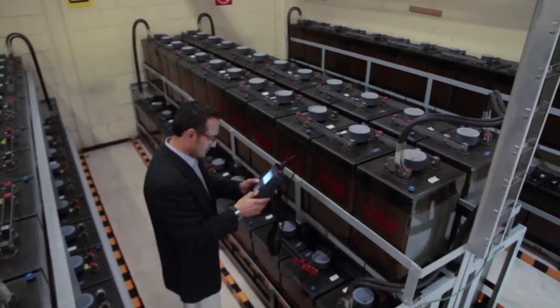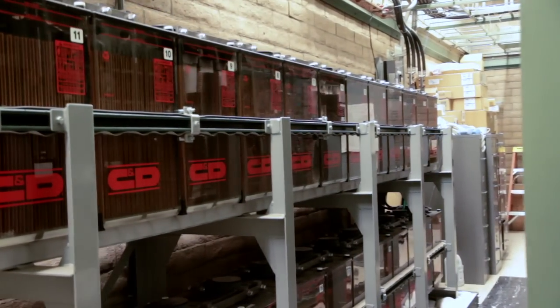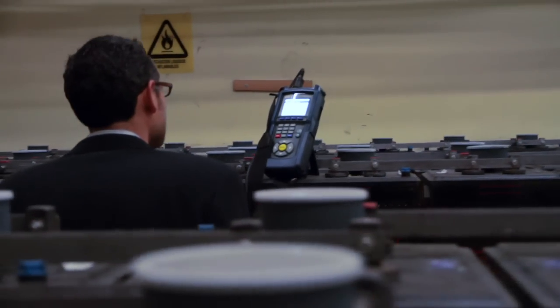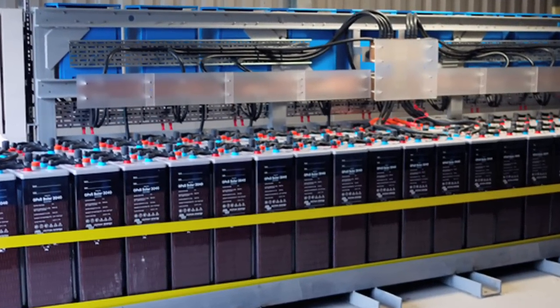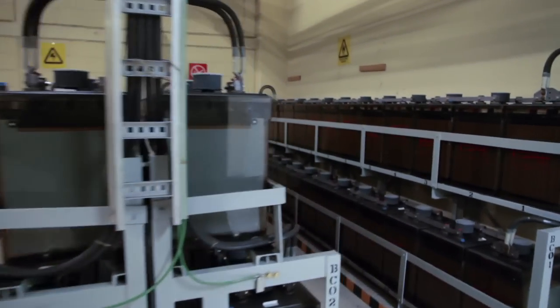One or more weak battery cells can and often will lead to the shutdown of a backup power system, and the resulting loss can be severe. Unless you can afford to wait for a power outage to reveal the condition of your backup system, regular testing of the batteries is essential. Annual capacity tests are recommended for any battery that has reached 85% of the expected service life or has a capacity below 90% of the manufacturer's rating. If the capacity is less than 80% of that rating, the battery should be replaced.